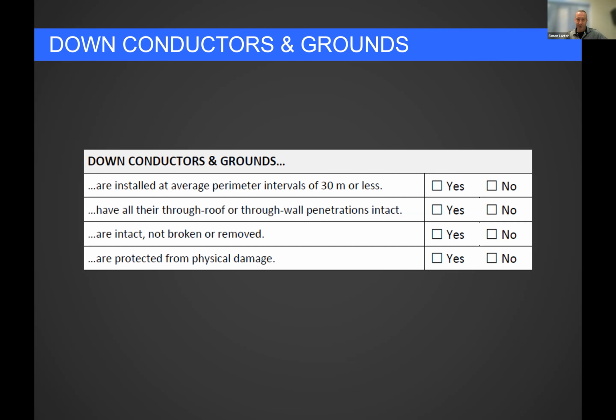But the down conductors and grounds, and you'll see this if you eventually give the document a read through, have to be installed at average perimeter intervals of 30 meters or less. The reason we do this is because, again, I've tossed around 20,000 amps of current. That's just what we test surge protectors at, but it's not by any stretch the most powerful lightning strikes on record. The most powerful lightning strikes on record go north of 200,000 amps. So 200 kiloamps of current going through. That's an awful lot of current.